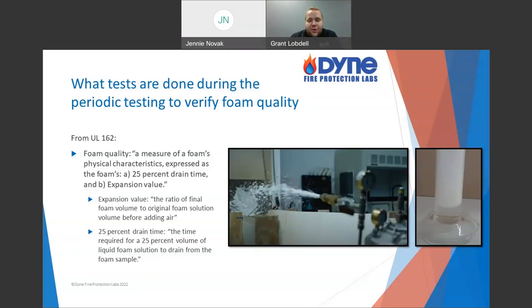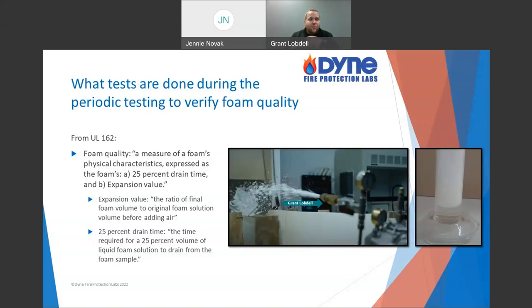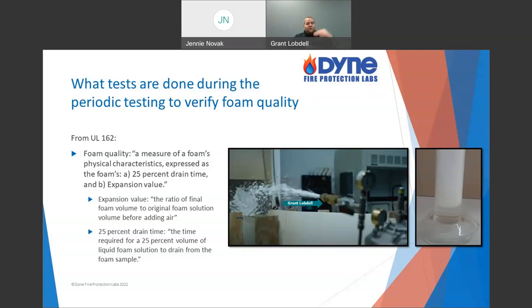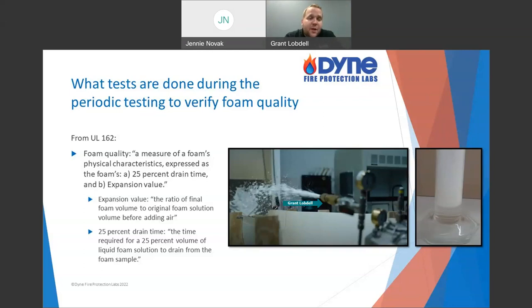What's expansion? What's shown on screen is an example of a test setup. Generally, you're going to make your solution at the concentration it's listed at or being used at. So if I have a 3% foam, we mix it up at 3%. We'll use our water, or yours if it's not municipal. We put it through this test nozzle, it hits against the backboard, we collect it. I started with a liquid and now it's been aerated — air is trapped in it and it's expanded, filling a larger volume. That's our expansion ratio.